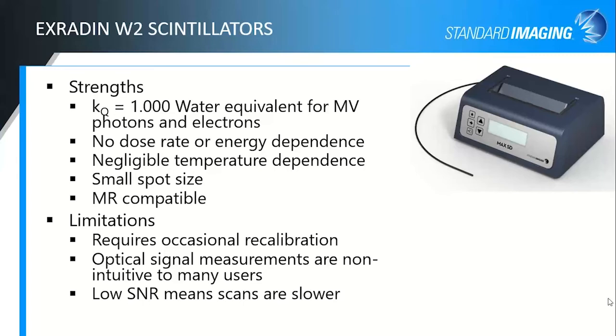So strengths of the W2, whoops, I think there was a question. Looks like the W2 can be used comfortably to measure a 1 by 1 centimeter field. Yes, indeed. I have proof in the pudding. I think in the next slide, I have seen 5 millimeter fields measured with it. I'm not sure about the 4, but yes, the major limitation really is signal level potentially if you've got a low signal strength due to that very high collimation, and the 1 millimeter detector size gives you some volume averaging there.